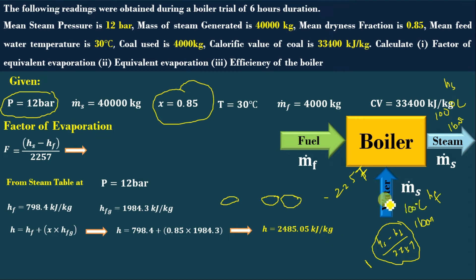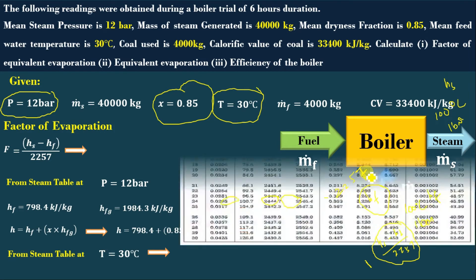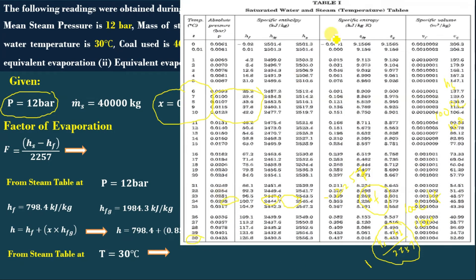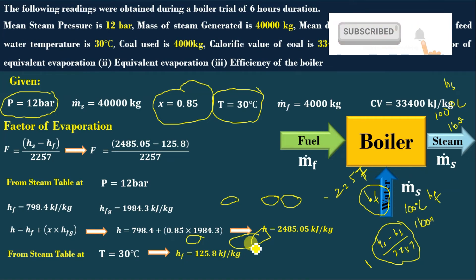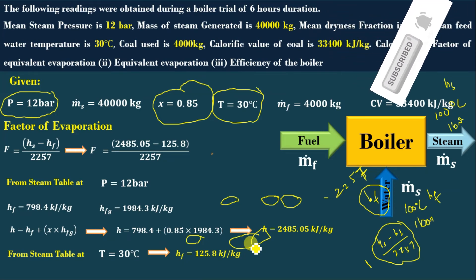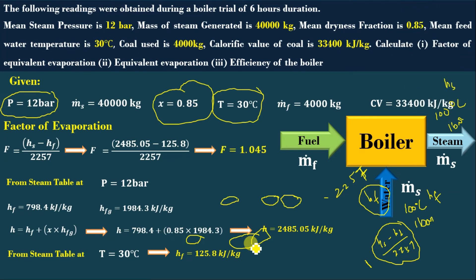Similarly, we need to find out the inlet enthalpy of the boiler feed water. We always take saturated liquid. The feed water temperature given is 30°C. From the steam table for 30°C, Hf = 125.8 kJ/kg. Now substituting in the factor of evaporation formula: F = (2485.05 − 125.8) / 2257 = 1.045. So it is 0.045 times greater than the actual evaporation.